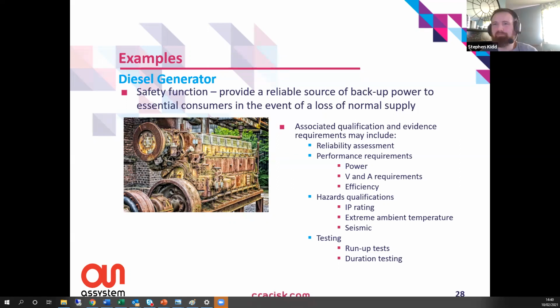So the main safety function is to provide a reliable source of backup power to essential consumers in the event of a loss in normal supply. So if we lose the grid, we've got all of our safety systems, we need to keep them powered. So that will be a safety function in the safety case, and that will drive a number of requirements on the diesel generator itself. So it's a very important function. It'll be a category A safety function. Effectively, the diesel generator will probably be a class 1 system, which will have a high reliability claim on it effectively. So we might have to do reliability assessment to underpin that.